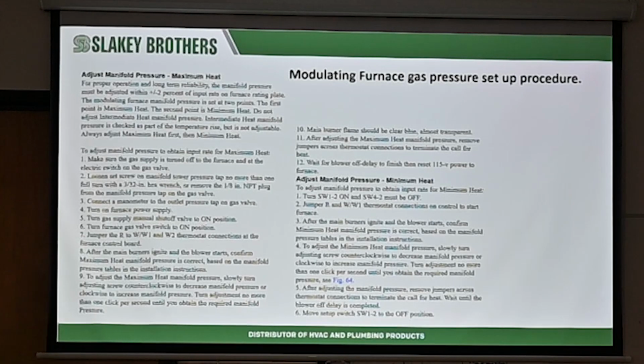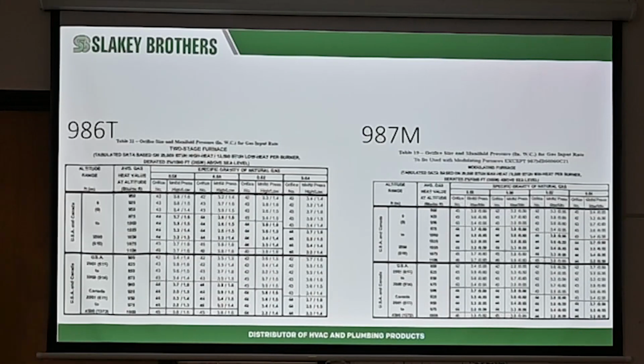You set the high. Then you've got to tell this thing that I am a two-stage thermostat controlled system, and you're going to turn on SW1 number 2, and then you've got to make sure SW4 number 2 is off. When these things are done this way, that's just telling the unit that I am a two-stage thermostat. I want you to work as a two-stage heating unit, even though it's modulating. So now when you call for W1 only, that's where you set your low fire rate. Okay? Your low fire rate is pretty low. So 987M.